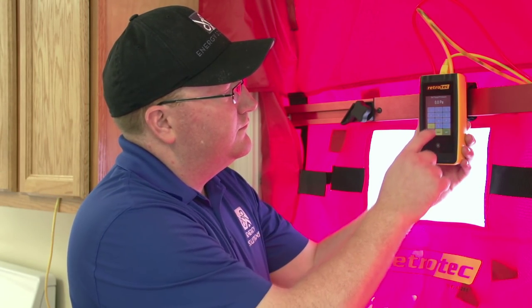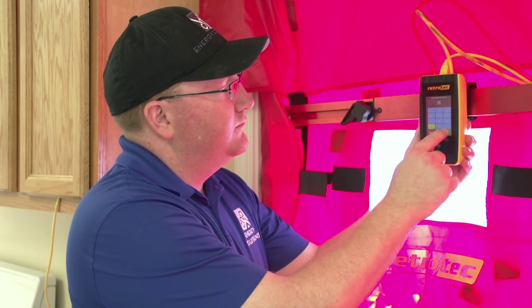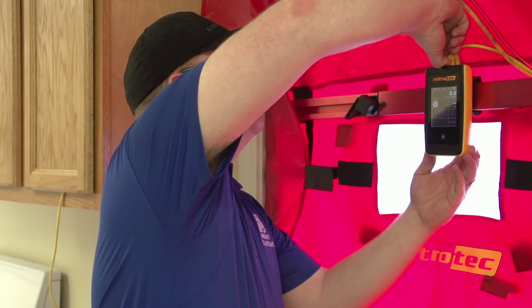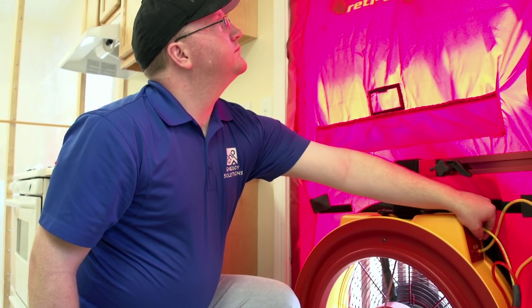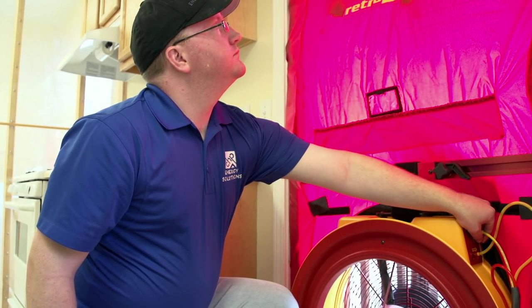There are three methods to operate the Retrotec fan: you can use the gauge's set pressure or set speed functions, or the speed control knob on the fan body. It is recommended that if you are just learning to use the DM32 Smart Gauge and the Retrotec blower door, you should disconnect the speed control cable and run the fan by turning the speed control knob on the fan body instead of utilizing the gauge to control the fan.